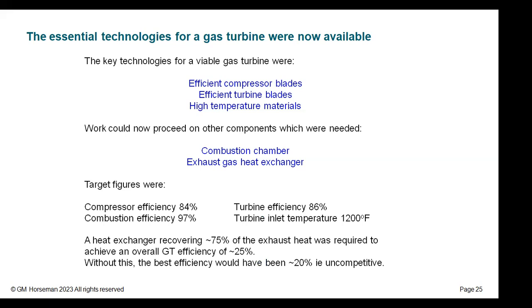The sort of figures that we're aiming for are stated here. These are from the original reports. 84% compressor efficiency, turbine efficiency 86, combustion efficiency 97, and a peak turbine inlet temperature of 1200 Fahrenheit, with 75% of the exhaust heat being recovered. So for the first machine, the demonstration plant in effect, that is what they were going to go for.